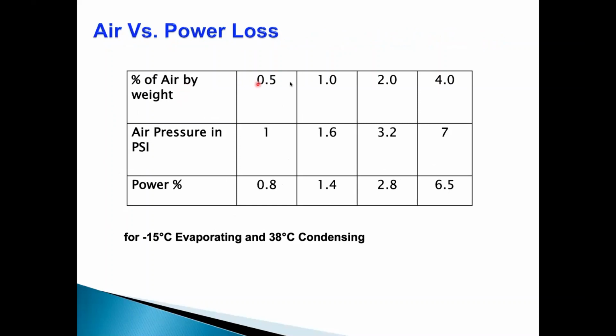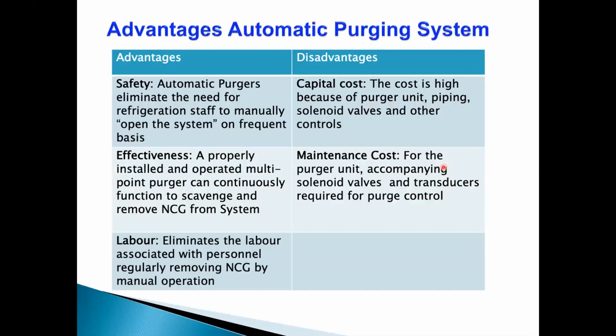Typically, this chart shows that if you have 0.5% air, your pressure will rise by 1 psi. But if you have 4% air, your pressure will rise by 7 psi. Then you have 6.5% excess power, which is very high when you're talking about a 500 kilowatt system. So what we have to do is put up an automatic purging system. An automatic purging system will continuously check the plant and remove any non-condensable gases or air.